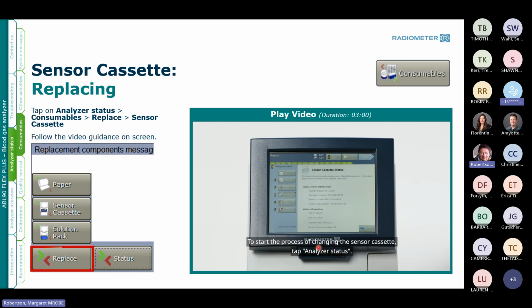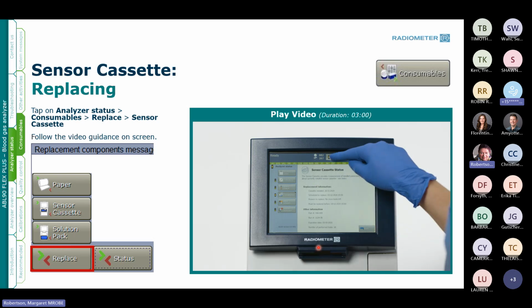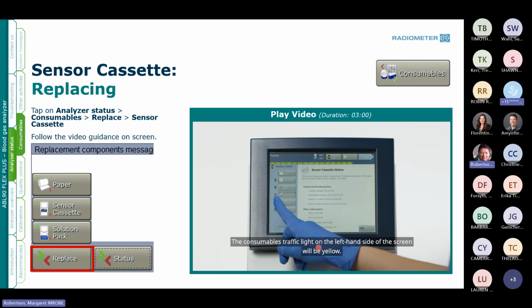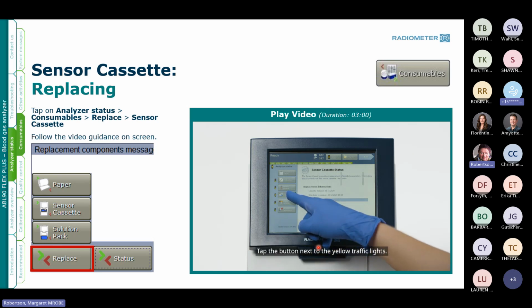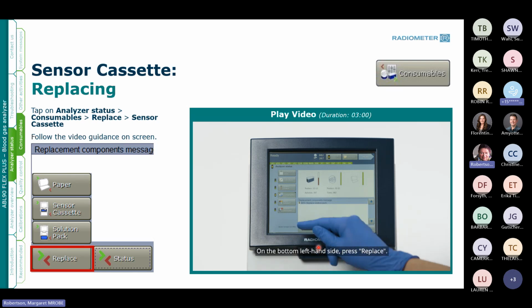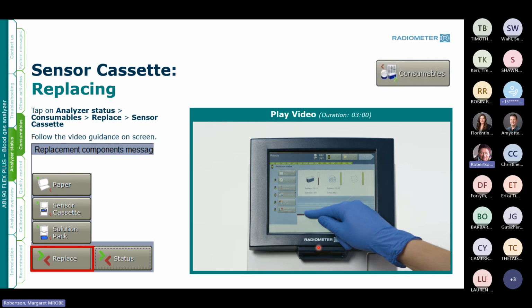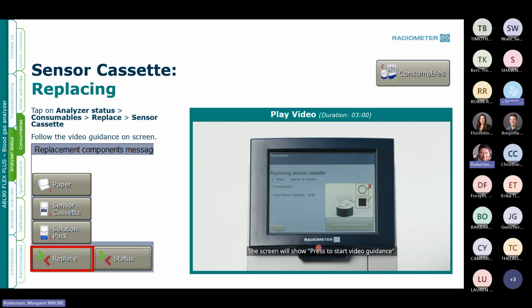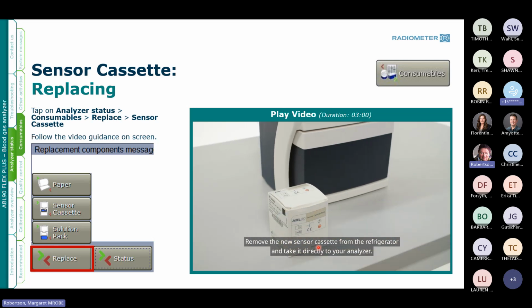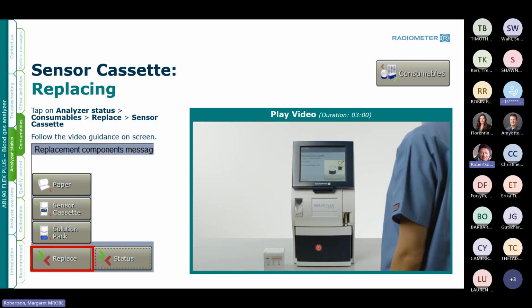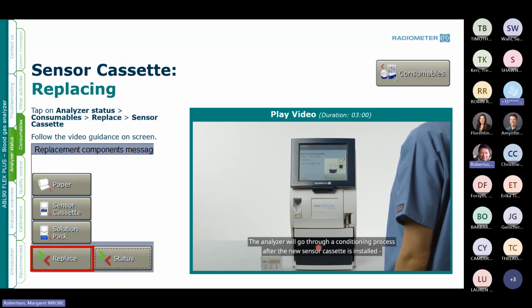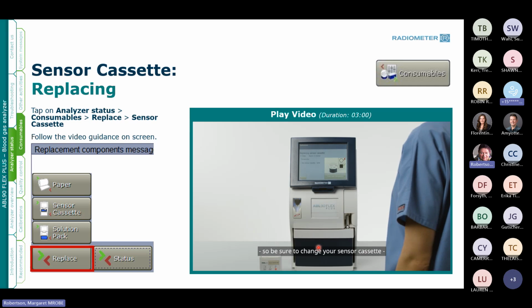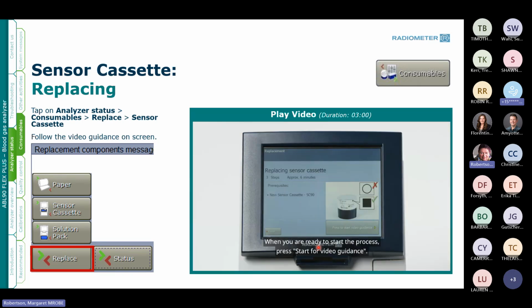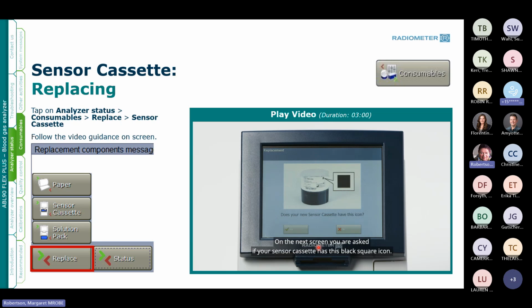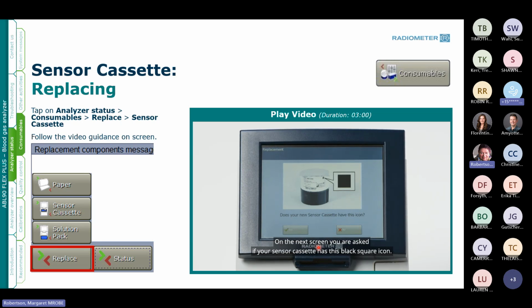To start the process of changing the sensor cassette, tap Analyzer Status. The Consumables traffic light on the left-hand side of the screen will be yellow. Tap the button next to the yellow traffic light. On the bottom left-hand side, press Replace. Choose the sensor cassette. The screen will show Press to start video guidance. Remove the new sensor cassette from the refrigerator and take it directly to your analyzer. The analyzer will go through a conditioning process after the new sensor cassette is installed, so be sure to change your sensor cassette when you anticipate a slowdown of incoming patient samples. When you are ready to start the process, press Start for video guidance. On the next screen, you are asked if your sensor cassette has this black square icon.